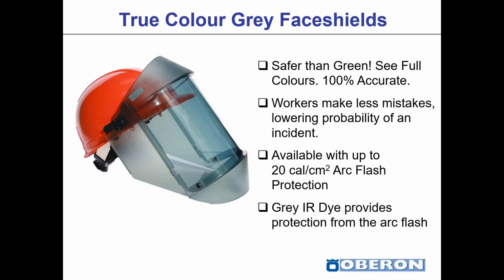It's actually the gray infrared dye, or IR dye, that provides the protection from an arc flash. If you recall a few slides ago, I showed that breakdown of an arc flash, and the first stage is that radiation wave. Well, that radiation wave contains the infrared that burns the worker. So traditional face shields in the market are green or have that green dye, which is an IR dye that activates to prevent that thermal energy from transferring through that material and burning your face. The newer technology available in the market is gray, which is safer than green in terms of color perception. And that gray is the IR dye and provides the protection from the arc flash.